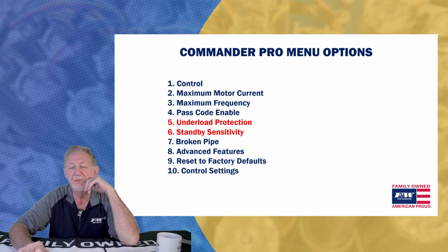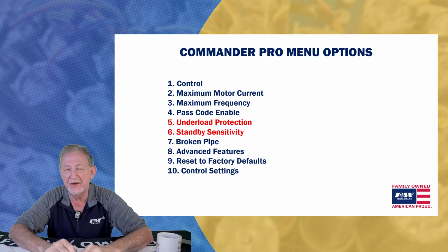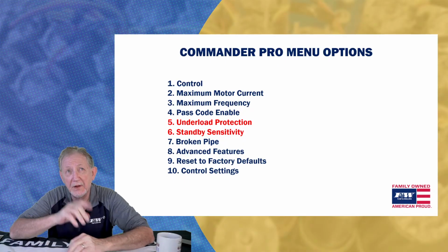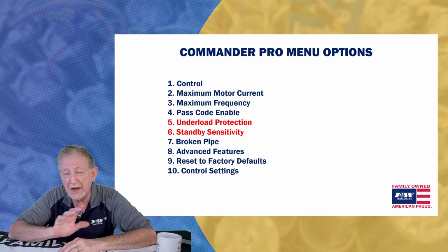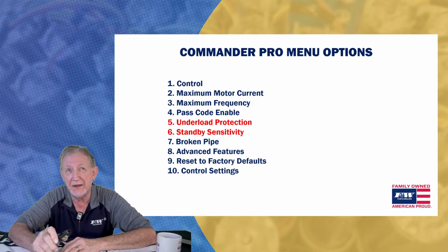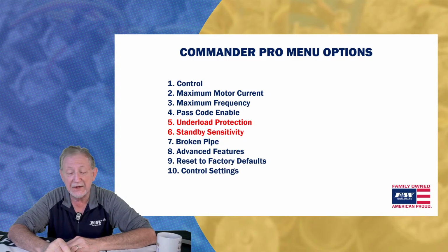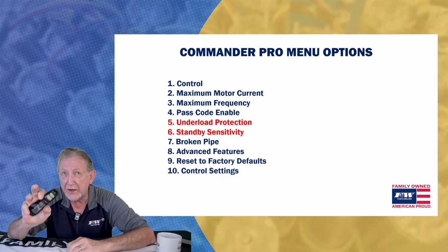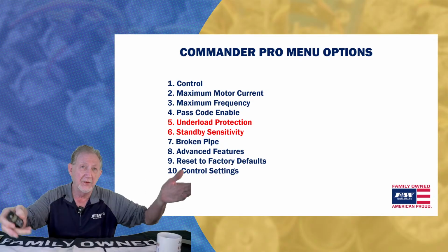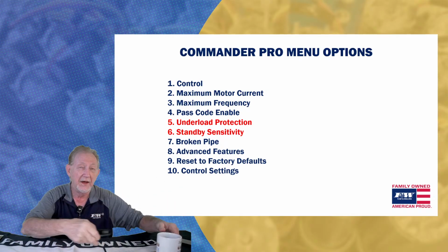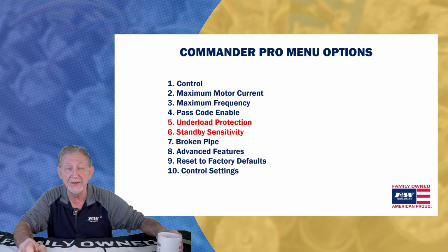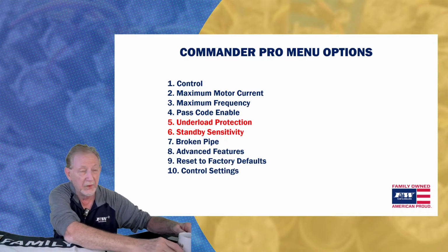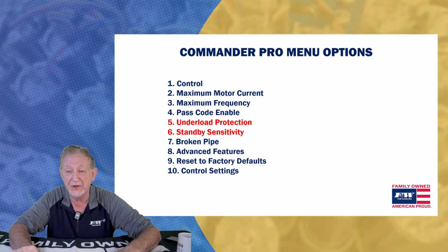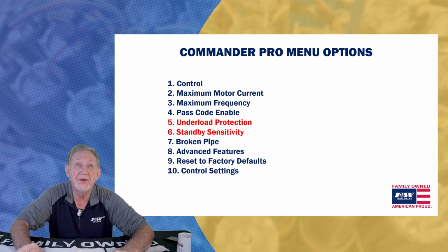Again, this whole thing was more around how to program this drive and set it up when you first install it. But I want to talk about number 5 and number 6 because, in my opinion, an understanding of those two will keep that drive from coming back off the wall and going back to the factory. There's often times that we can stand there and, just knowing how to tweak the drive, get out from underneath a fault that's been going on and causing us frustration. And the last thing we want to do is put a replacement drive on and the same darn problem's occurring, right? And that's happened more times than we like to talk about.